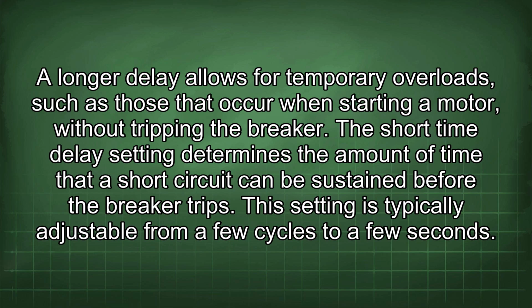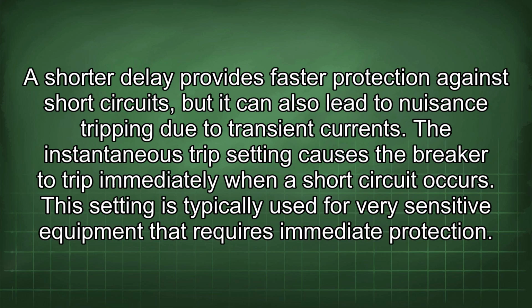The short time delay setting determines the amount of time that a short circuit can be sustained before the breaker trips. This setting is typically adjustable from a few cycles to a few seconds. A shorter delay provides faster protection against short circuits, but it can also lead to nuisance tripping due to transient currents. The instantaneous trip setting causes the breaker to trip immediately when a short circuit occurs. This setting is typically used for very sensitive equipment that requires immediate protection.